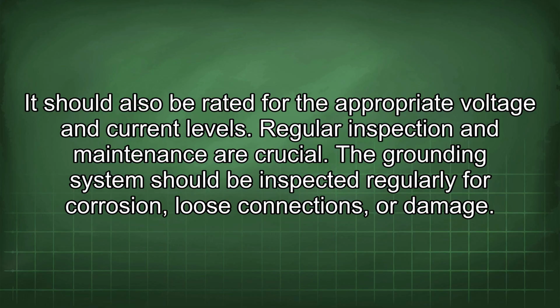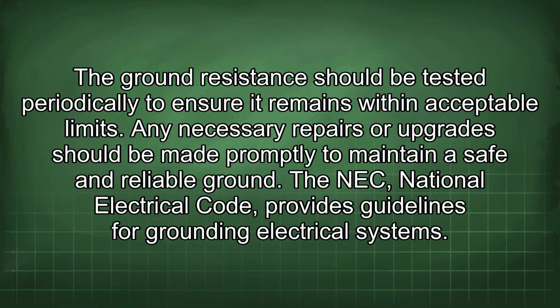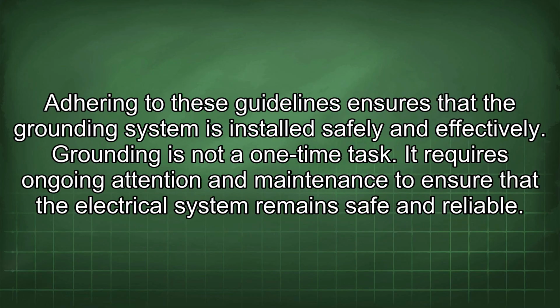The grounding system should be inspected regularly for corrosion, loose connections, or damage. The ground resistance should be tested periodically to ensure it remains within acceptable limits. Any necessary repairs or upgrades should be made promptly to maintain a safe and reliable ground. The NEC, National Electrical Code, provides guidelines for grounding electrical systems. Adhering to these guidelines ensures that the grounding system is installed safely and effectively.